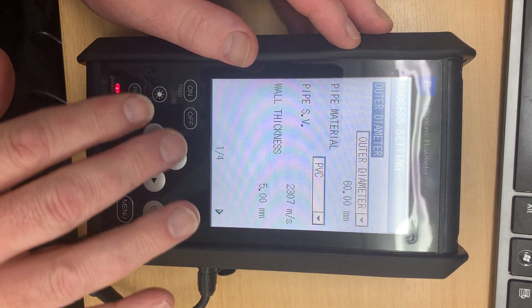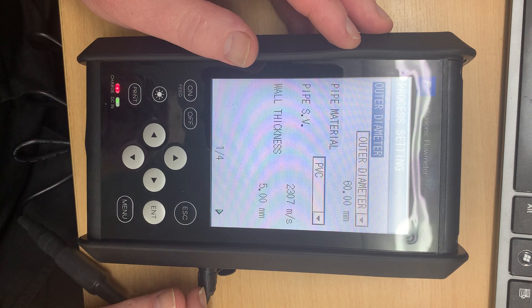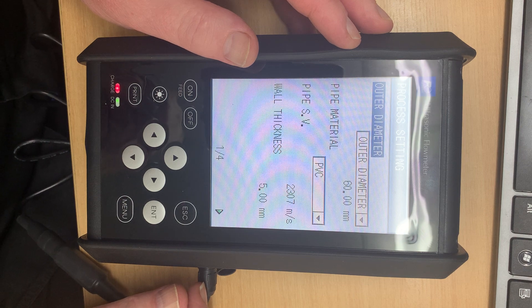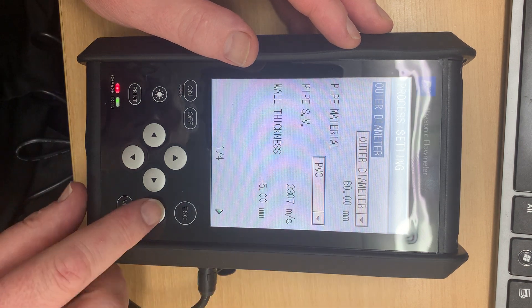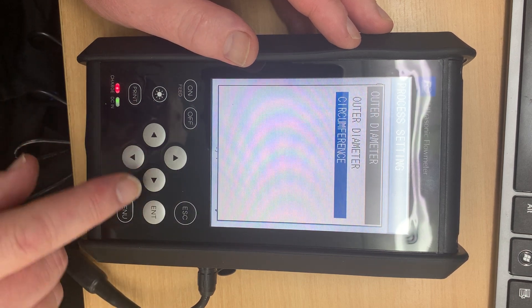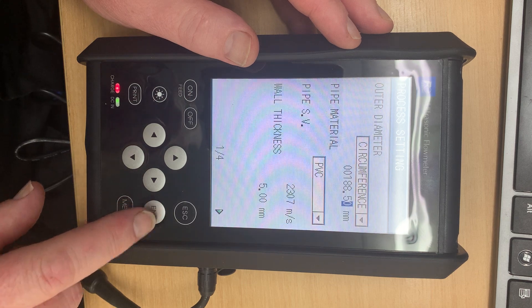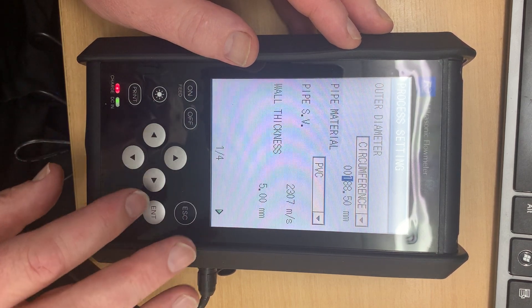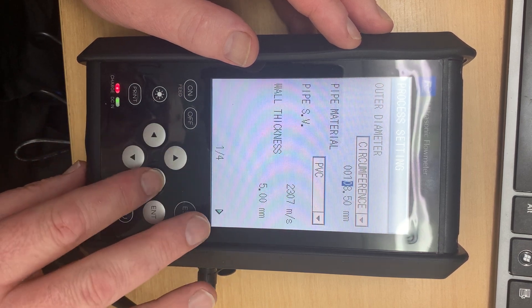There are four screens to go through here, only a couple of which you'll probably use. So first of all we want to set the outer diameter of the pipe. That can either be the circumference or the outer diameter. Circumference is nice and easy and then we simply put in the pipe size. So let's say in this case the pipe is 100 millimetres.